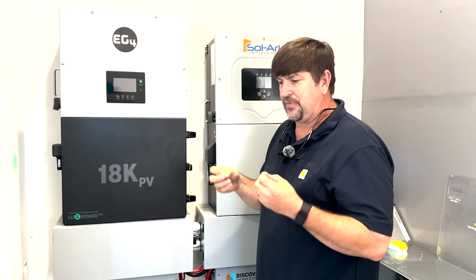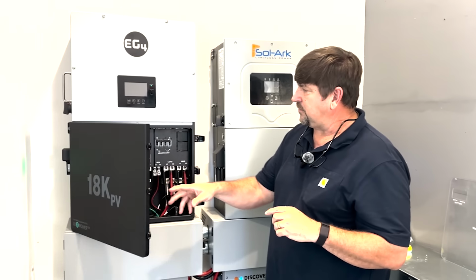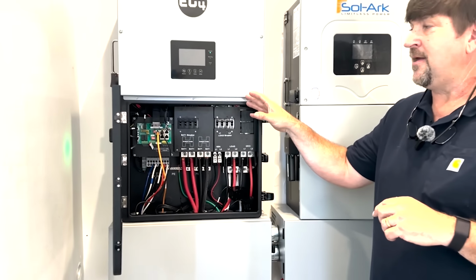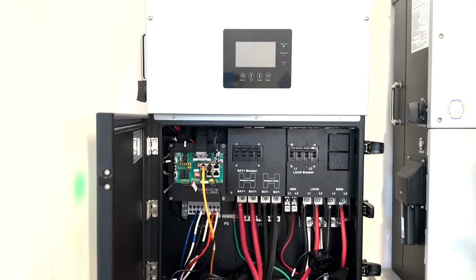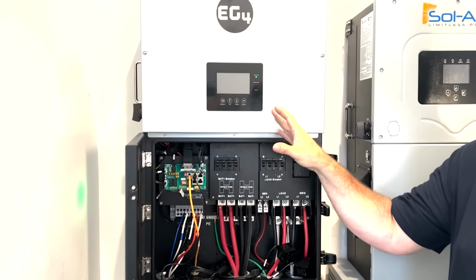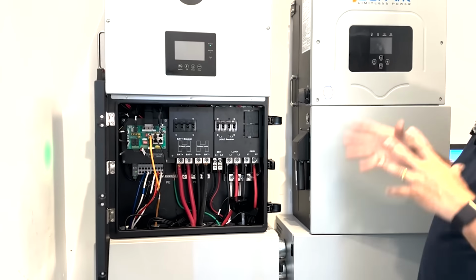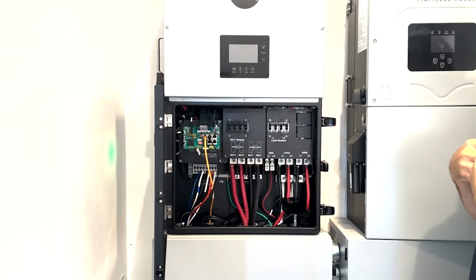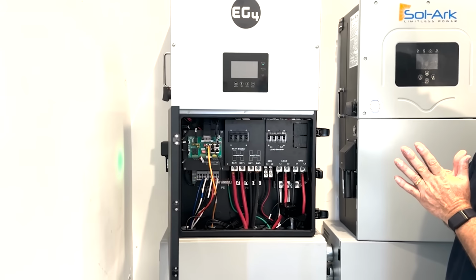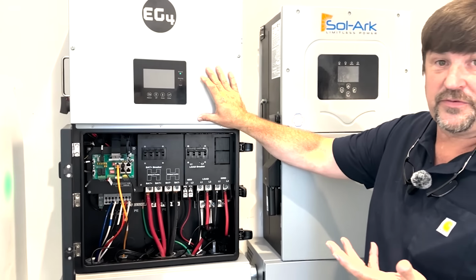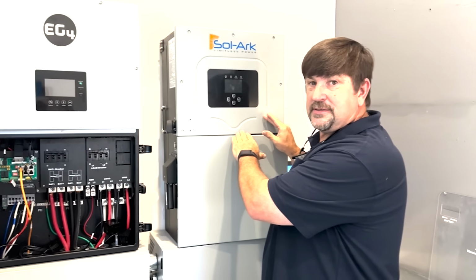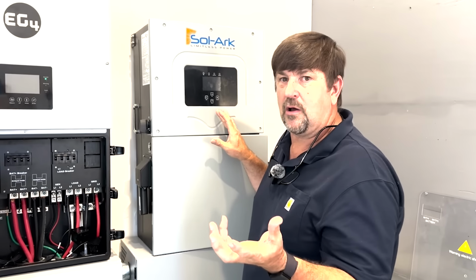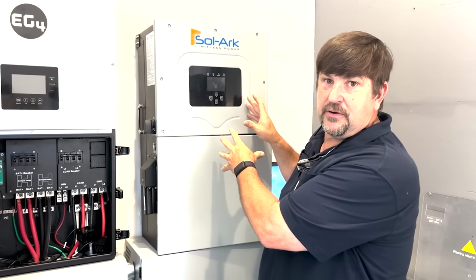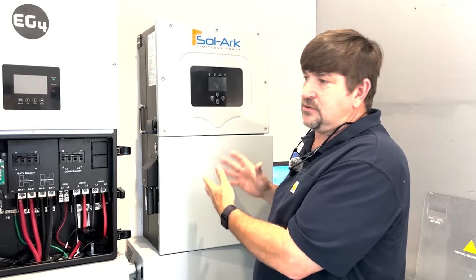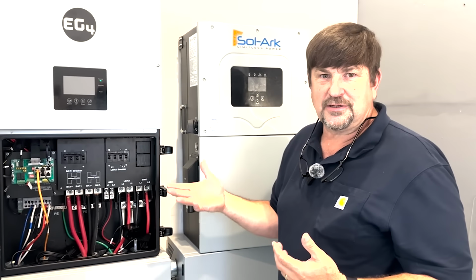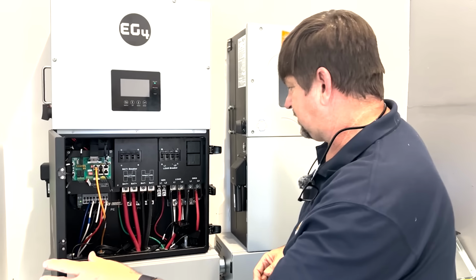To add to that, I could be wrong, but I don't think there are any field serviceable repair parts like grid relays. A lot of the relays in here are soldered in, not field serviceable. This one is fully assembled in Texas from individual parts, while the other is made in China and sent to Signature Solar or EG4 Electronics. I never saw a list of field service parts. When there's a failure, which has been rare, I've replaced things like a loose screw on a grid relay, just a quality issue. But I can replace the grid relays, boards, MCU boards, control boards, and screens in this machine. I don't think you can do that with the EG4 inverter at this point.